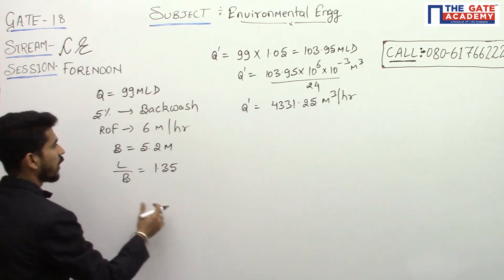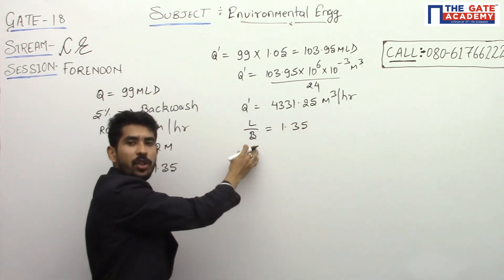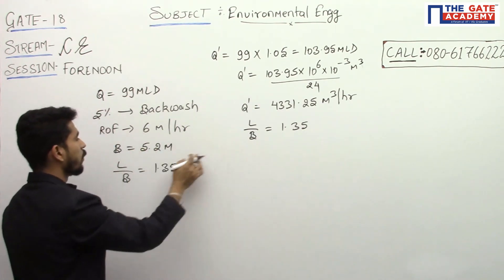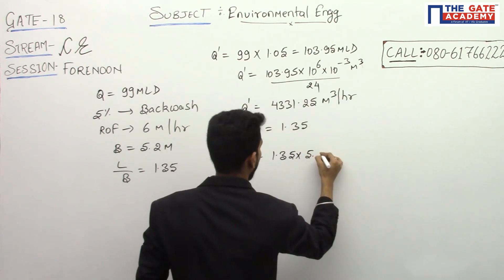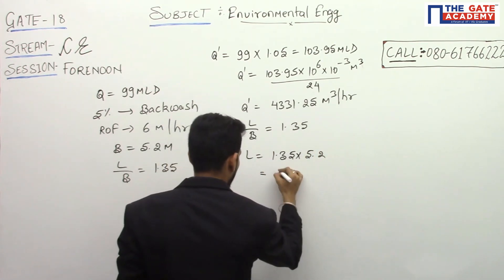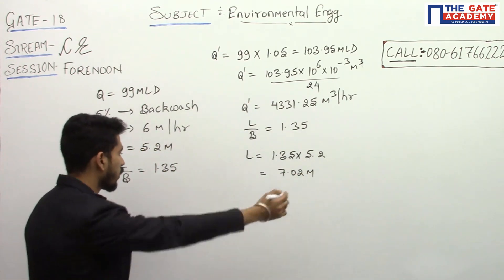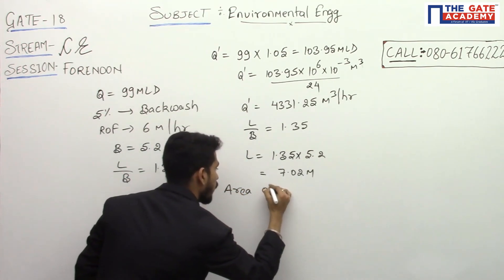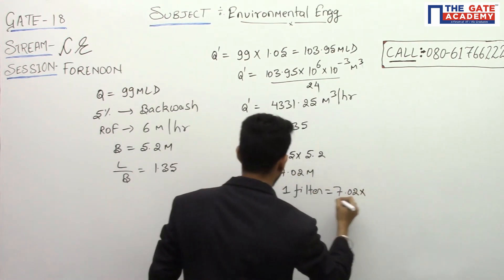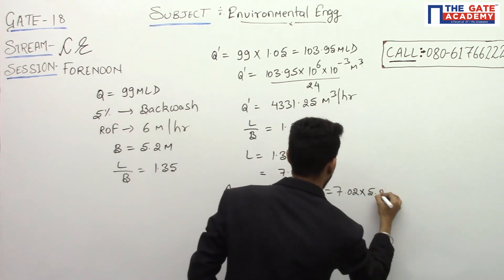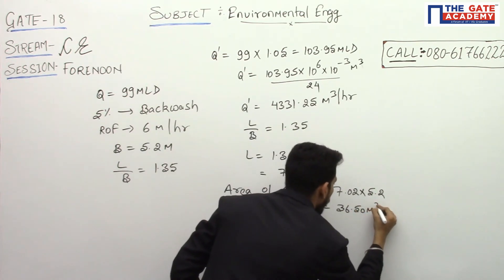Now, L by B equals 1.35 and the width of each filter is 5.2 meters. So L equals 1.35 into 5.2, which gives L equal to 7.02 meters. We now have the length and width of one filter. Area of one filter equals 7.02 into 5.2, which equals 36.50 square meters. This is the area of one filter unit.